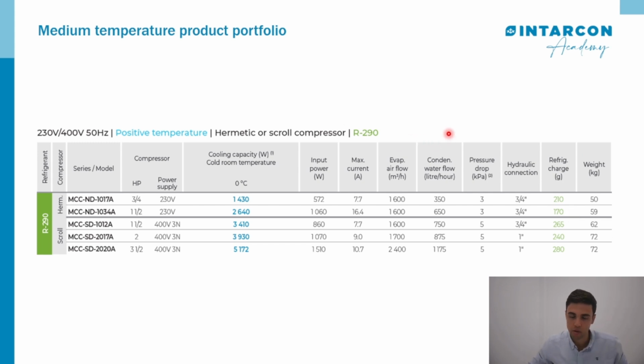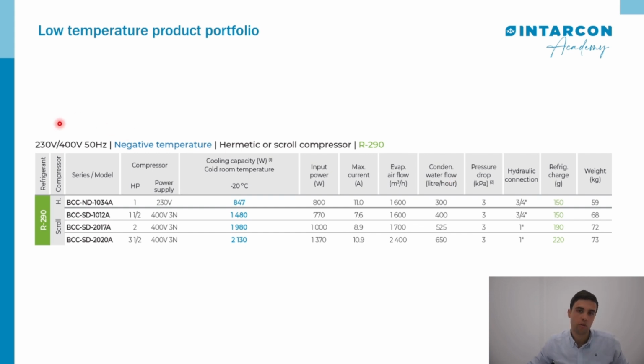In this column we see also the condenser water flow, in liters per hour, for exchanging the condensing power that we have created. It's important to dissipate and calculate next the pump. Next, the low temperature portfolio product, the part of the compressor. We only have a single model with a reciprocating hermetic compressor. The other will be with a scroll. We obtain a cooling capacity range for a cooled room temperature of minus 20 degrees, from 800 watts up to 2 kilowatts.